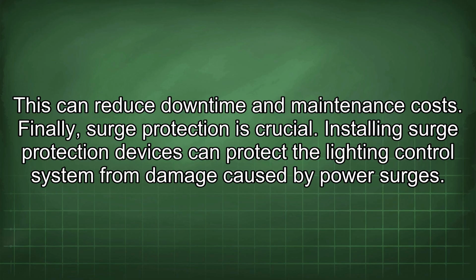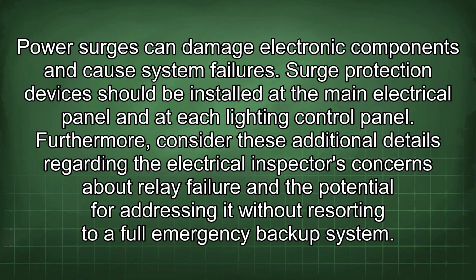Finally, surge protection is crucial. Installing surge protection devices can protect the lighting control system from damage caused by power surges. Power surges can damage electronic components and cause system failures. Surge protection devices should be installed at the main electrical panel and at each lighting control panel. Furthermore, consider these additional details regarding the electrical inspector's concerns about relay failure and the potential for addressing it without resorting to a full emergency backup system.